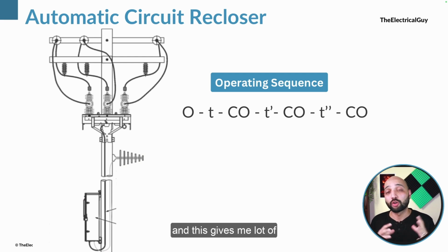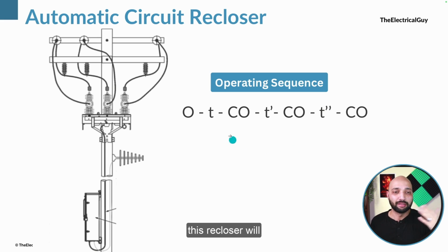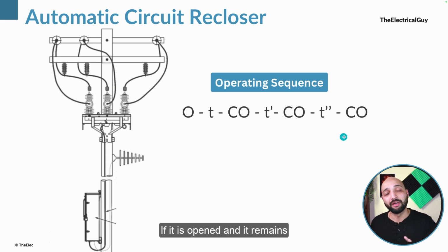And this gives me a lot of advantage because I don't need to go every time a fault occurs to check whether it's a permanent fault or a temporary fault. This recloser will take care of that. If it is opened and it remains open for a long time, that means the fault is permanent and I need manual intervention, right? Clear? So that is what we call the operating sequence, which is given by the IEC standard.